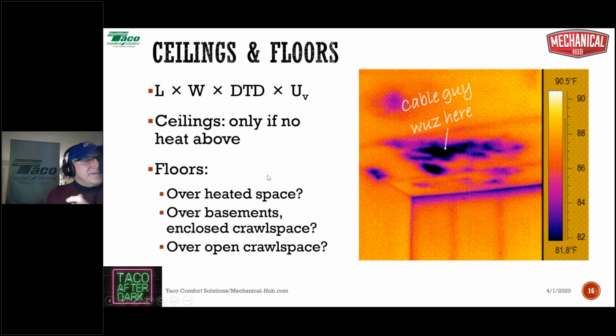Floors are similar but different - it's about whether there's a heated space below. If you're on the second floor with a heated first floor below, skip this step, there's no floor loss. If you're over an unheated or unconditioned basement, or an enclosed crawl space - kind of like a mini basement - same idea. IBR says you really don't have to do a floor loss in that instance.